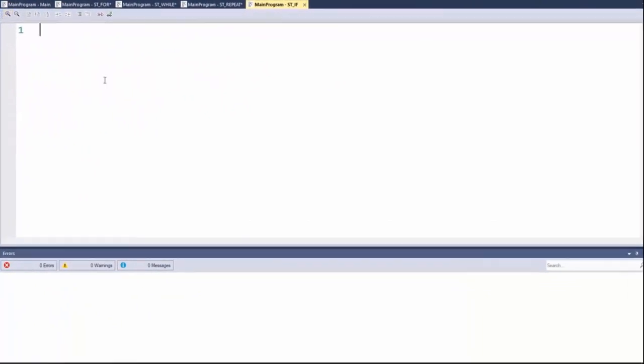To demonstrate the if-then constructs, this time we will not use the code snippet. Use if-then to complete an action when specific conditions occur. According to the code that we have developed so far, we can use the if-then construct to reset the value of the tags used within the iteration loop. Let's first reset the tag named counter when its value is greater than 1000. When the counter value is greater than 1000, the controller will assign 0 to the counter.